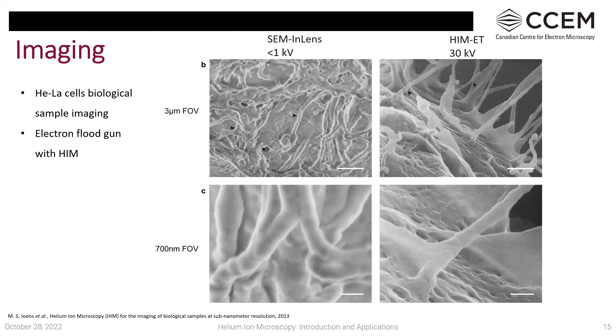Moving to the applications section: one of the best published comparisons shows an SEM image with an in-lens detector versus a helium ion microscope image with the ET detector, both of a biological sample with no coatings. On the HIM, an electron flood gun neutralized positive charge. The HIM image is very clear — the features and edges of HeLa cells are visibly sharper. The SEM was optimized below 1 kV landing energy, yet the zoomed comparison clearly shows higher resolution with the HIM.